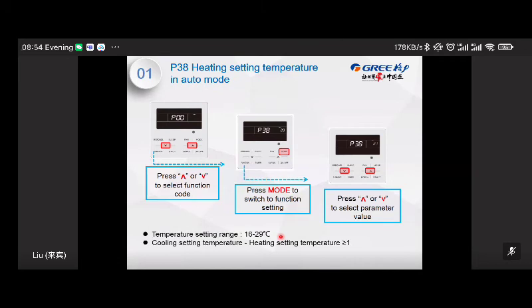P38, that's the heating setting temperature in auto mode, and range is 16 to 29 Celsius degree. However, just remember that the cooling setting temperature minus heating setting temperature should be higher than 1 degree. Yeah, they cannot be the same.